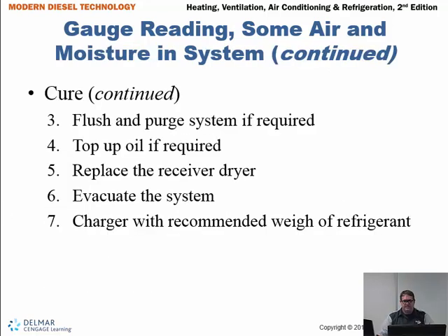All right, gauge reading, some air and moisture in the system. So the cure again: flush and purge the lines, top up with oil, replace the receiver dryer, evacuate the system, and charge with the recommended weight of refrigerant.